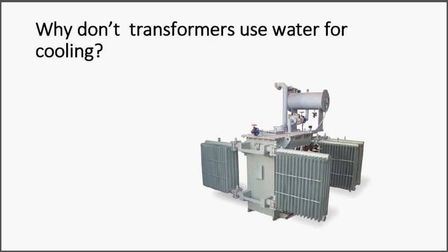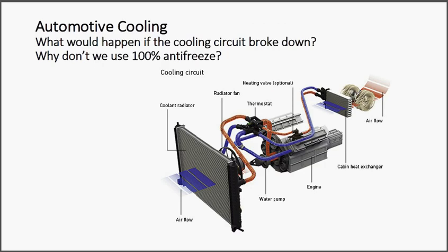We need oil, especially if there's potentially a small fault in the insulator around the transformer windings. The oil doesn't mind; it copes without a problem. It adds to the insulating properties, and that's the reason why we use oil in transformers and we can't use water.